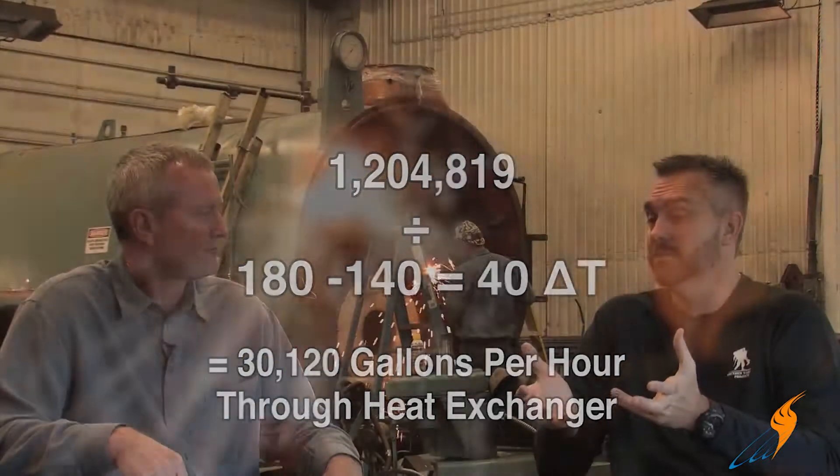You're basically trying to size a heat exchanger for that particular job. Typically what we'll do is use a steam boiler and a heat exchanger as a converter to give them the hot water. That way I can take a 250-horsepower boiler and one heat exchanger and supply a load from 4 million BTU up to 8 million BTU, giving a real wide range to size that heat exchanger.